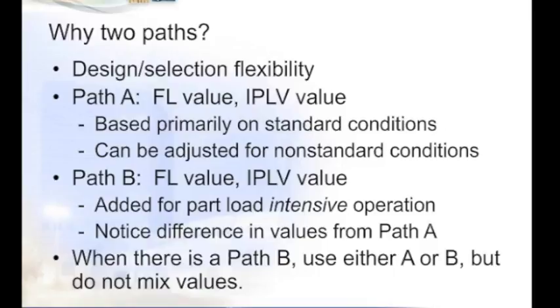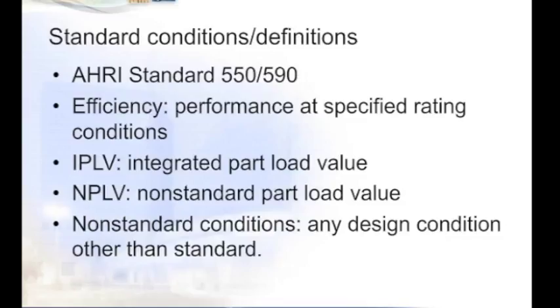So let's talk about standard conditions and definitions for a minute so we can better understand what the 90.1 standard is, as well as what changed in this addendum. The current AHRI, which is the Air Conditioning, Heating, and Refrigeration Institute, standard 550/590 has been around a while, but it was updated, and the current version is the 2011 version. Its title is the Standard for Performance Rating of Water Chilling and Heat Pump Water Heating Packages Using the Vapor Compression Cycle. That's a mouthful, but the real reason is because it establishes the testing criteria that manufacturers must use in order to get their equipment rated.